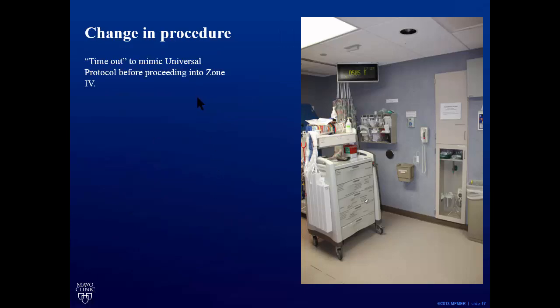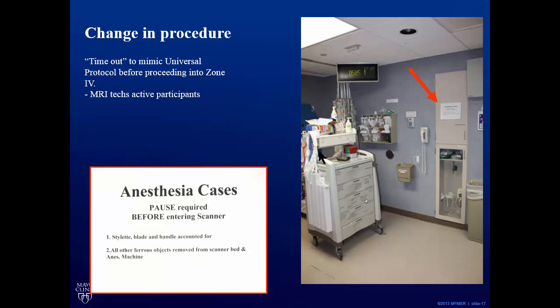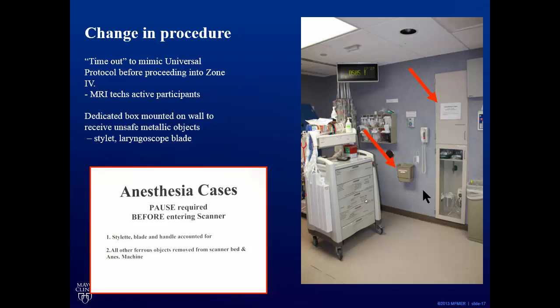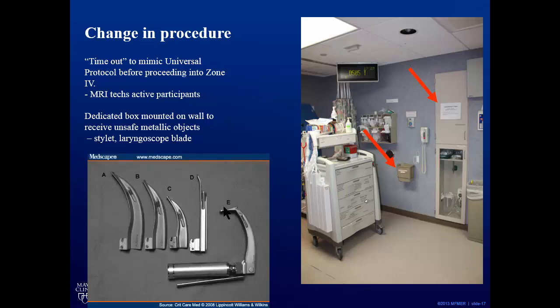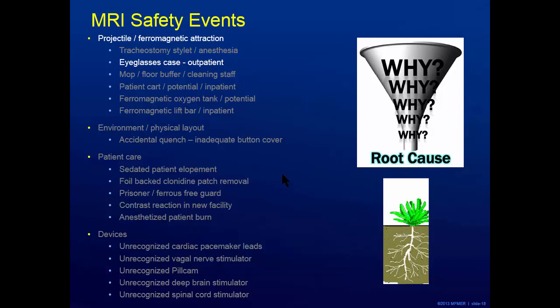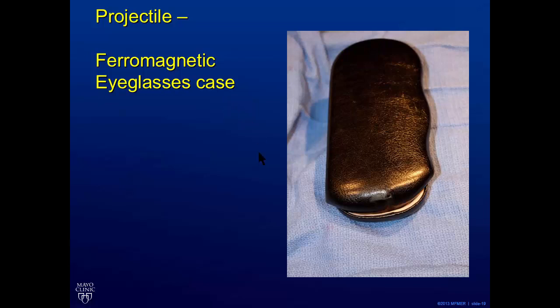We changed our procedure. We now have a timeout to mimic the universal protocol before proceeding into the magnet room. The MR techs are the ones who implement this, and we put a dedicated box on the wall to receive the stylet and the laryngoscope blade, which can also have ferromagnetic components in them. Another incident we had involves a ferromagnetic eyeglasses case.